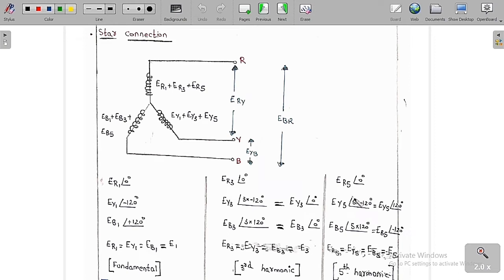Similarly, if I go for the fifth harmonic component, ER5 is at an angle of 0 degree since 5 into 0 is 0. EY5 is 5 into minus 120, which simplifies to plus 120 degree, and EB5 is 5 into plus 120, which simplifies to minus 120 degree. If you draw the phasor diagram, we get rotation in the anti-clockwise direction, giving RYB. So this is opposite to the phase sequence of the fundamental, and we say this is the negative sequence, the fifth harmonic voltages.